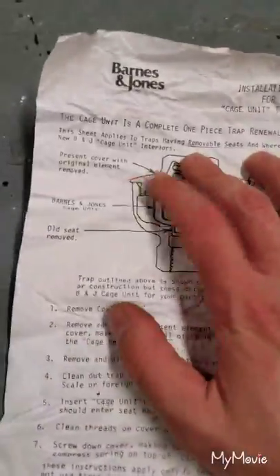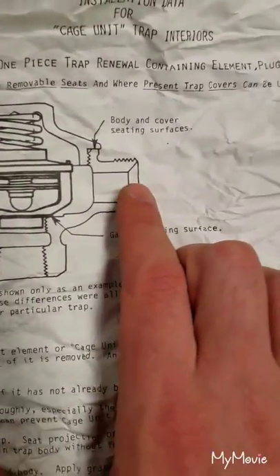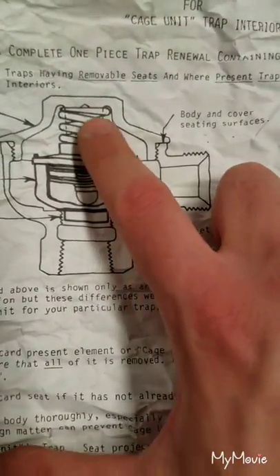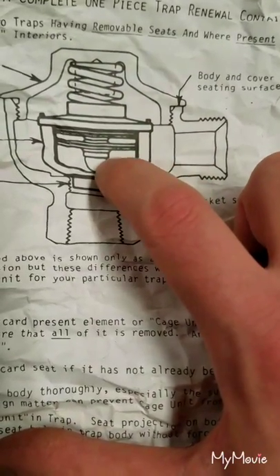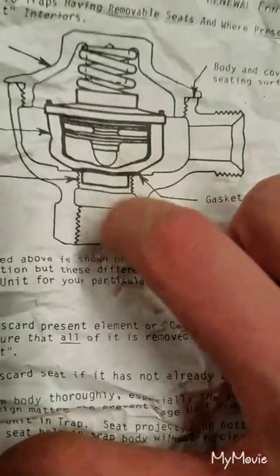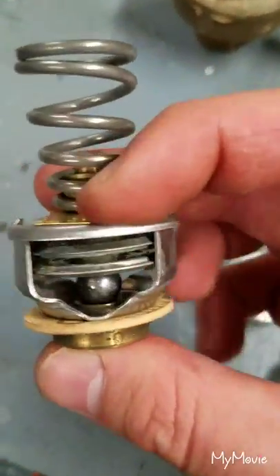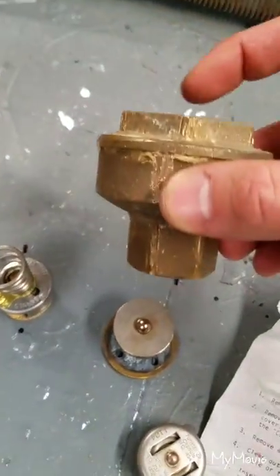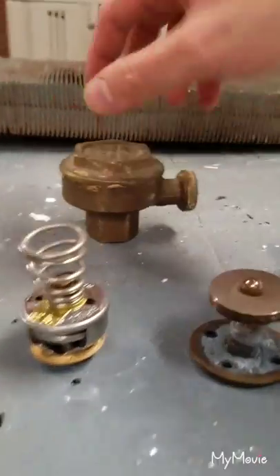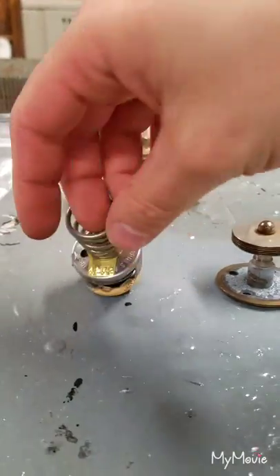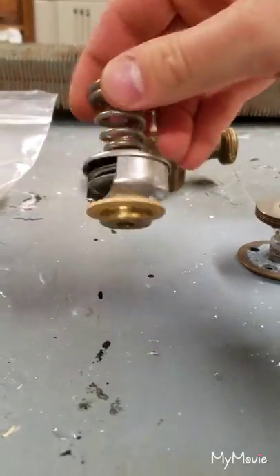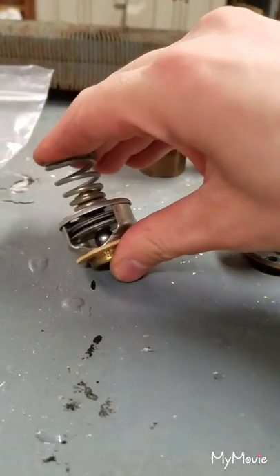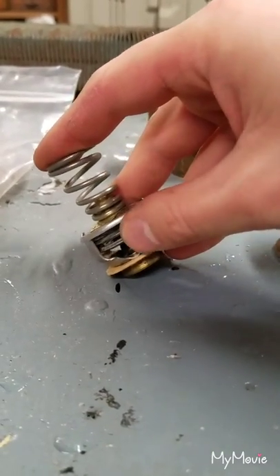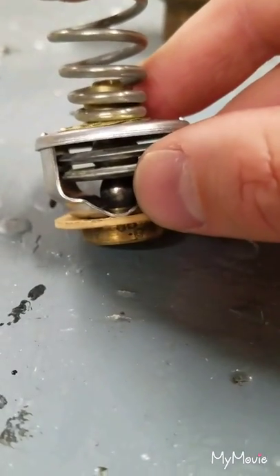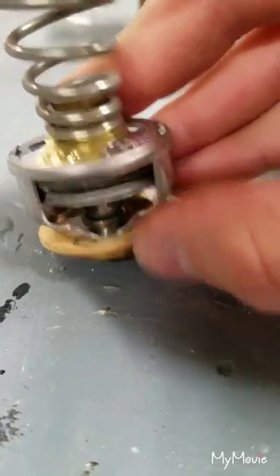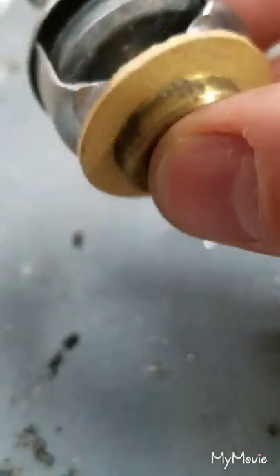So this is a Barnes & Jones. As you can see, this is a steam trap. So steam's coming in here. Spring. Element. Element heats up. When the steam comes in, lifts up, lets the condensate out. That element's right here. So what happens, here's another steam trap, is, for example, you would take this cap off, hold back on the pipe 2 inches, this element would drop inside. This is for a different trap, obviously, a bigger trap. But this spring gets compressed on the top, which compresses this. Steam comes in here. It heats it up. This expands back, lifts that little ball up, and the condensate comes out the bottom here.